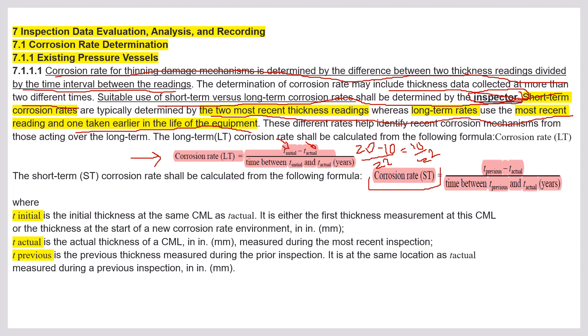For short-term, t_previous is used — the thickness from a prior intermediate inspection, not t_initial. For example, if another inspection was done in 2010 and t_previous = 15 mm, and t_actual now in 2022 = 10 mm, the time interval is 2022 − 2010 = 12 years. Short-term corrosion rate = (t_previous − t_actual) / interval. T_initial is the initial thickness at CML; t_actual is the current CML thickness; t_previous is the thickness measured during the prior inspection.